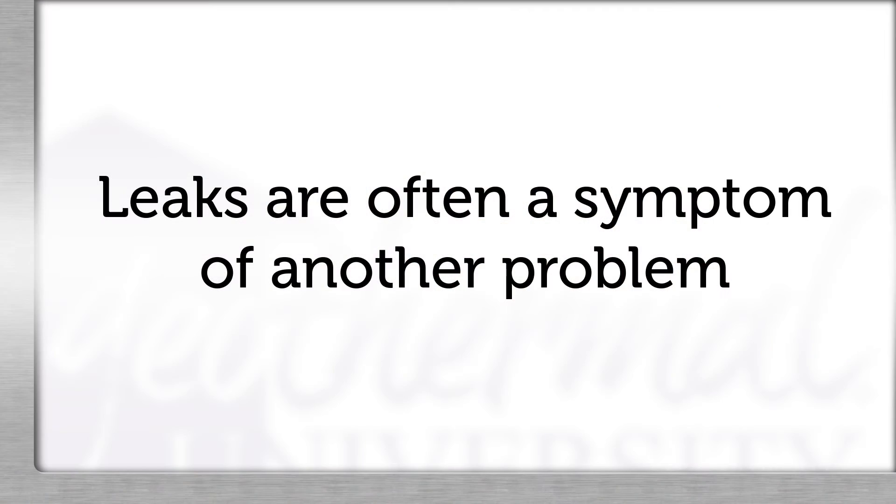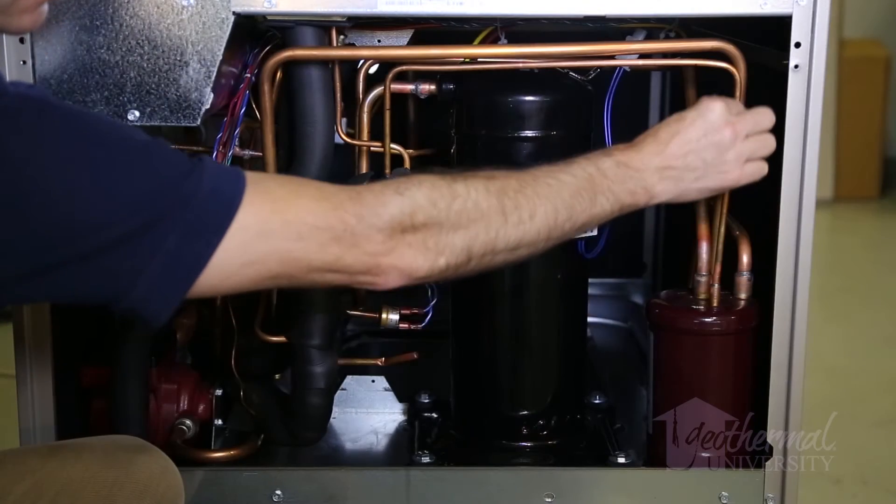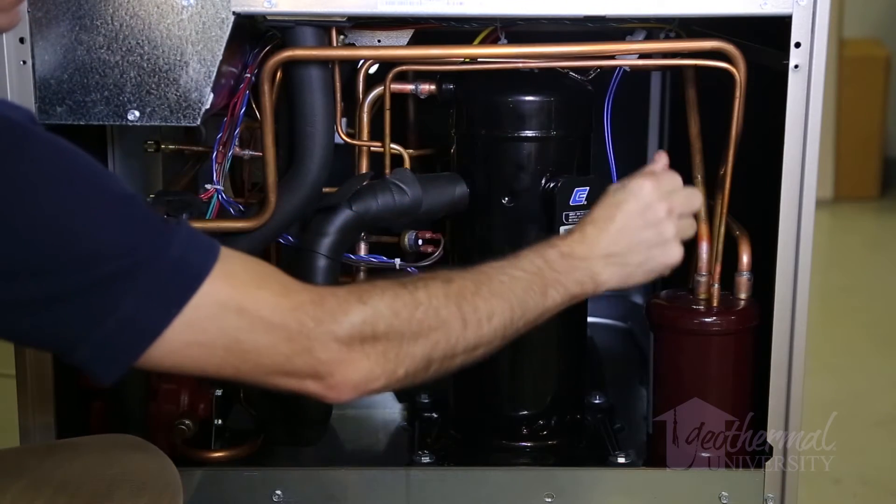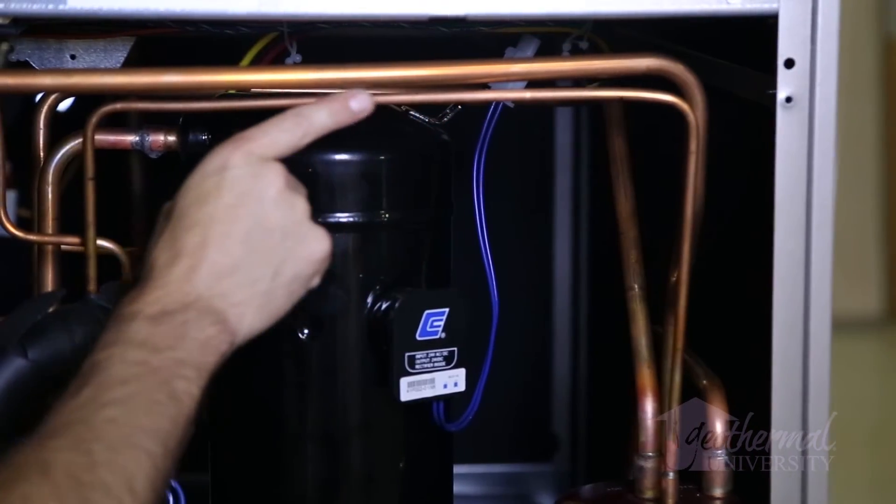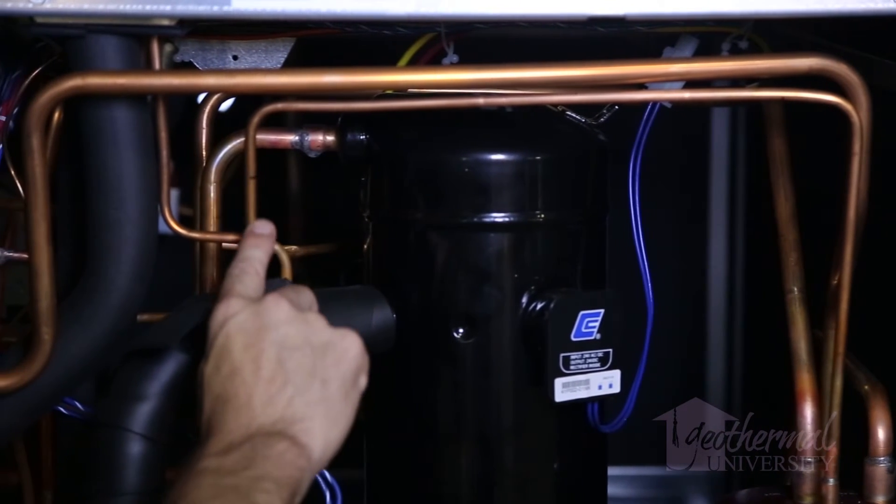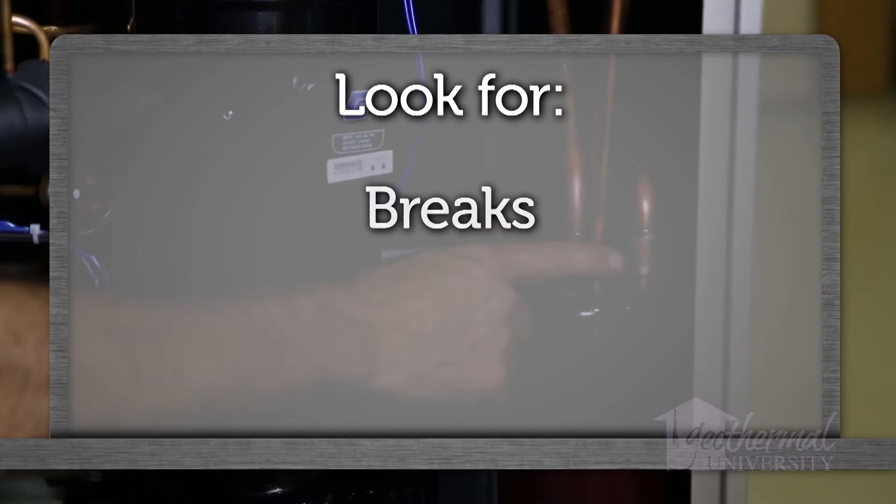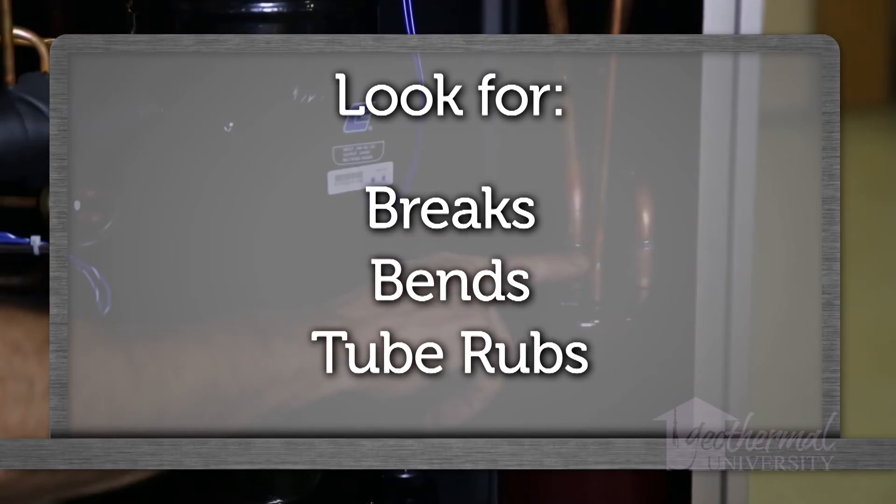Leaks are often a symptom of another problem. For example, many leaks result from vibration. Equalizer lines, process tubes, or refrigerant ports may have been subjected to mechanical vibration. Look for breaks, bends, or tube rubs.